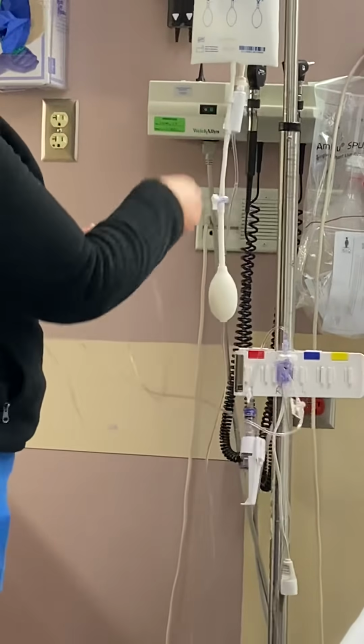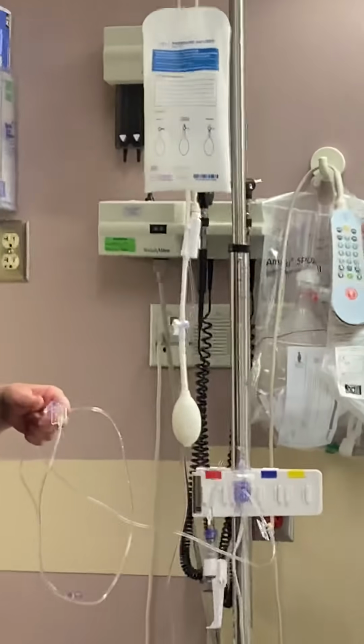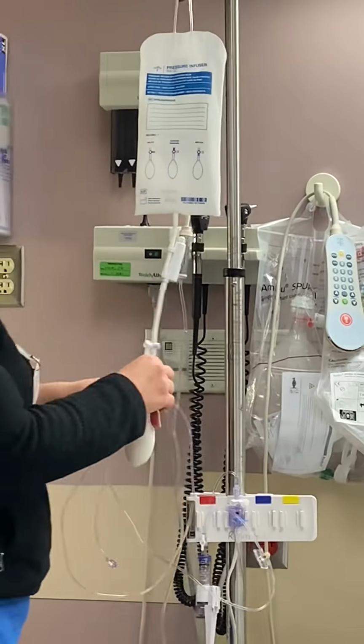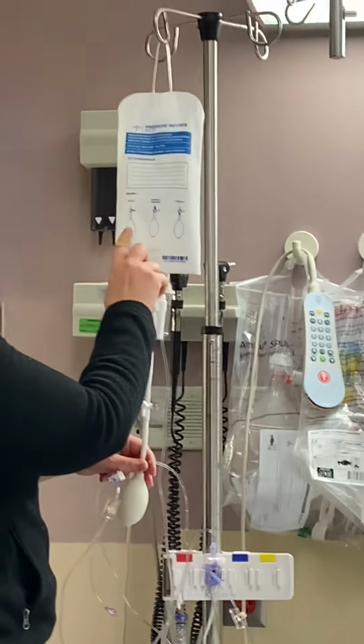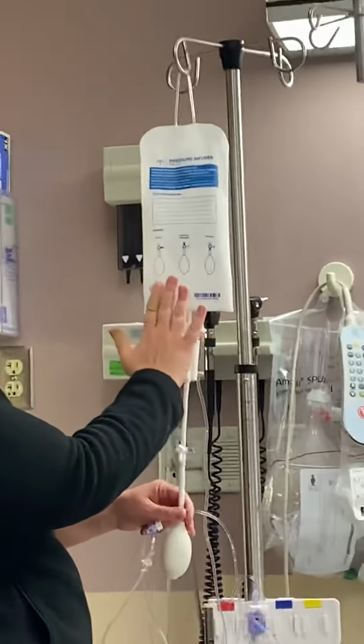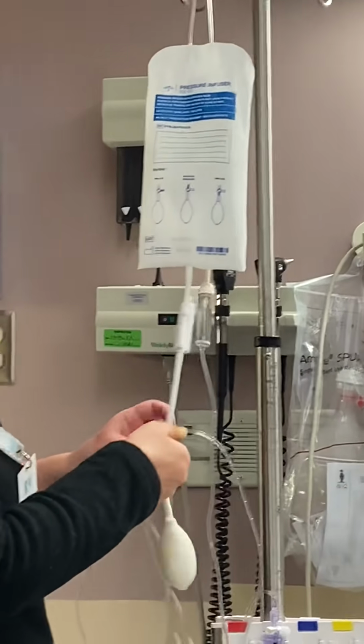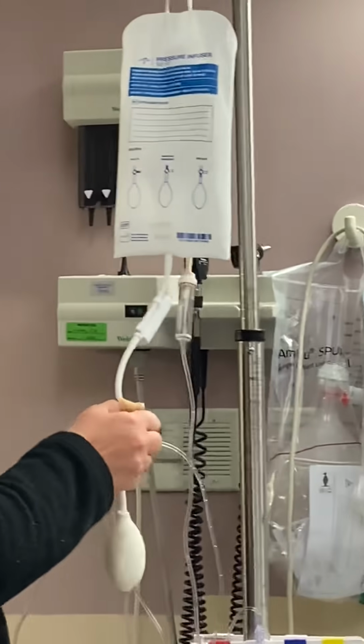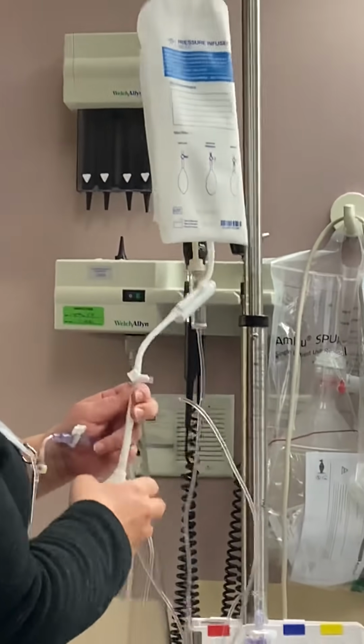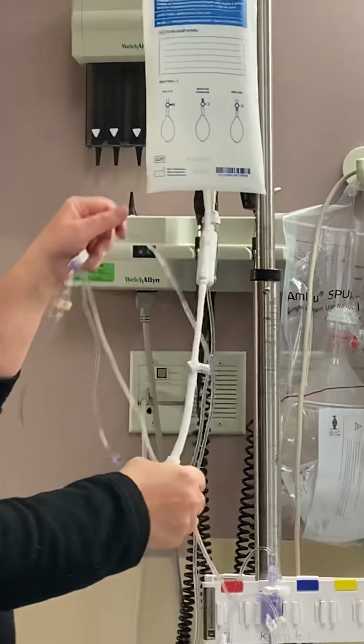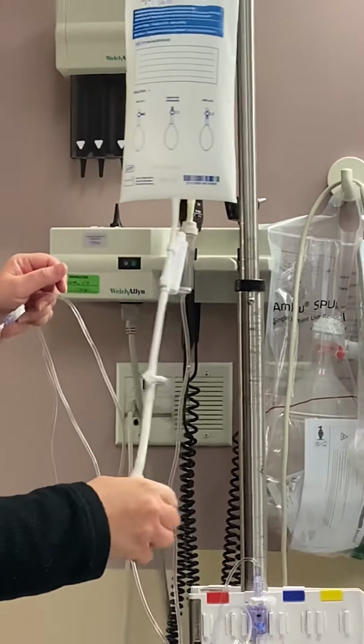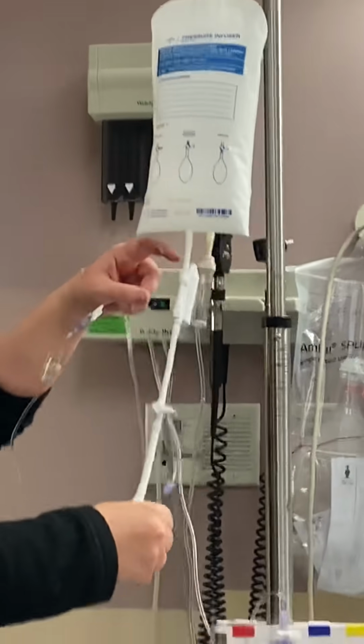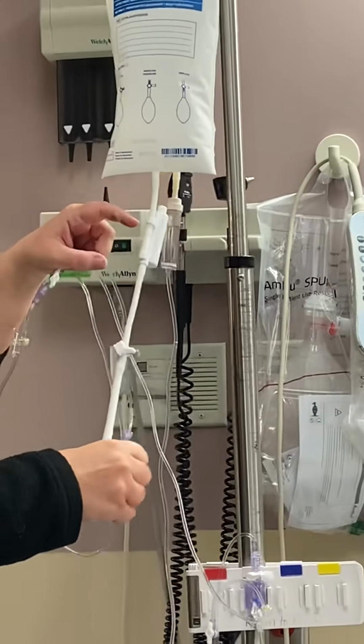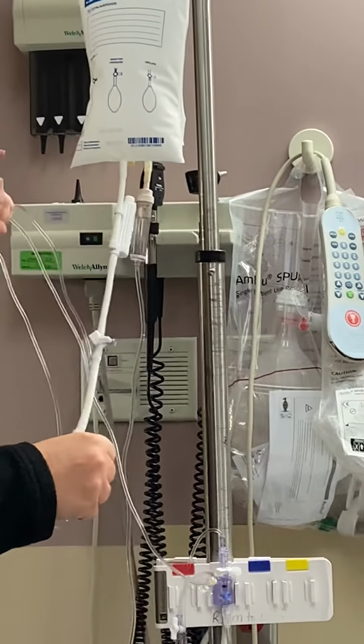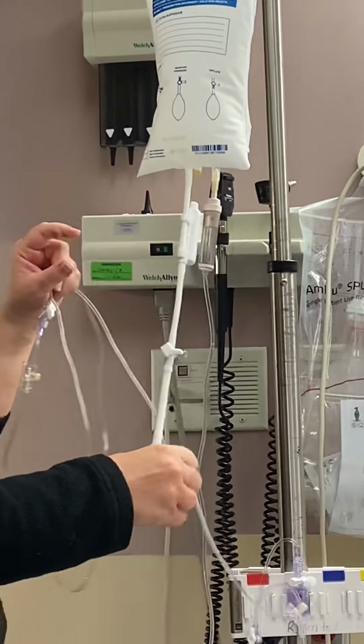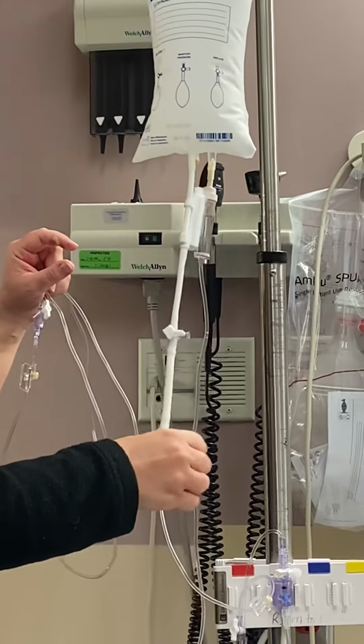Put this under pressure. It needs to be pumped up to 300 millimeters of mercury. And so what I'm going to do is follow my instructions here. There's a nice visual on the outside of the bag that tells you which way to turn the valve. So I need to keep it flush with the 0 port to inflate my bag. And I'll know I have it up to that 300 when this little popper pops up and you'll see a green section of this to designate we've got it up to the right pressure.